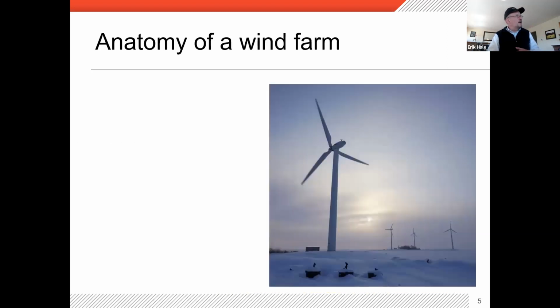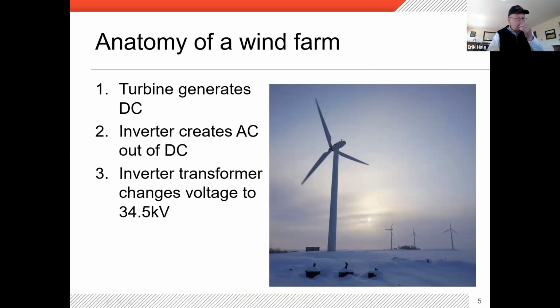I'd like to start off with the anatomy of a wind farm. This is a picture of a wind farm in a nice winter setting. At the top of the shaft is the nacelle, where there's a generator that, when the blade spins it, generates direct current. That feeds into an inverter, which creates AC out of the DC, still at low voltage. Then a cable runs down the shaft of the turbine to a transformer at the base that transforms the low voltage AC to 34.5 kV.